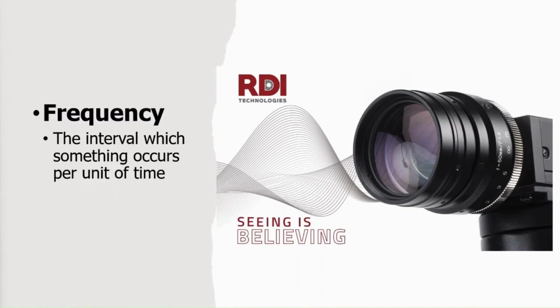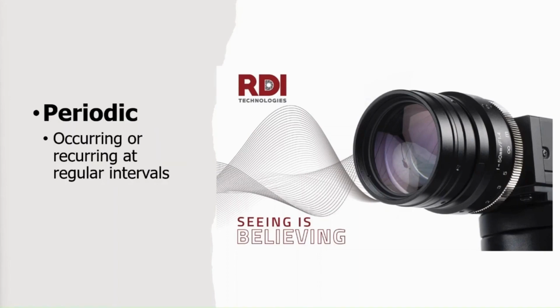Next, I'd like to talk about the frequency of the vibration. And the term frequency means the interval at which something occurs per unit of time. And another term that I'm going to use right now is the term periodic. Most of the time when we're analyzing things in our vibration spectrum, we are looking at periodic vibration, which basically means the motion or the vibration happens in a pattern. It recurs at a regular interval. The opposite of periodic would be transient, where transient would be more of a random type of motion or vibration.